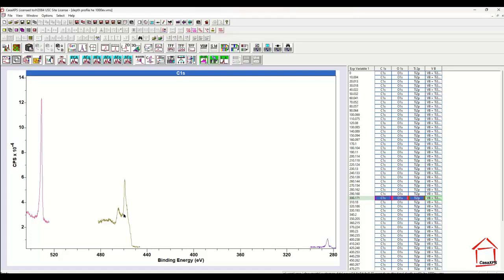And this in itself is useful information, particularly in this case because we have oxygen and the titanium very close in binding energy. So variables such as escape depth and the transmission function are relatively low risk when we try to do the quantification, in the sense that the kinetic energy of both of these peaks are similar, therefore the influence of the transmission and the escape depth will be similar. So we ought to be aware that this is rather a special case. If we're looking at salt, where we're looking at sodium and chlorine, then the separation of the 1s for the sodium and the 2p for the chlorine, for example, would be widely separated in kinetic energy, and we would then have to be very concerned about escape depth and also the transmission of an instrument.